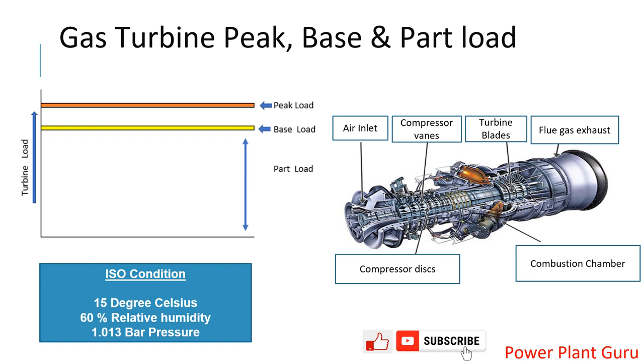So what should we consider as the full load condition of this machine? Full load condition is also called base load condition, which is the condition the machine is designed to operate at continuously. To clear this doubt arising from different ambient or site conditions, ISO conditions are defined by the equipment manufacturer. ISO conditions are standard conditions in which specific parameters are set — inlet air temperature is 15 degrees Celsius and relative humidity is 60% RH.